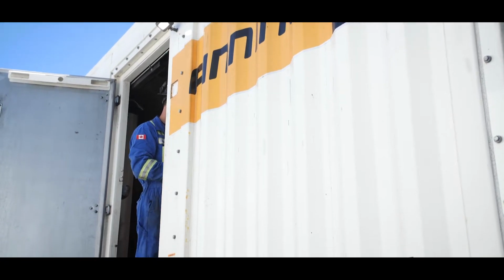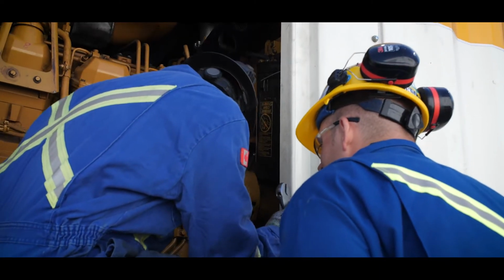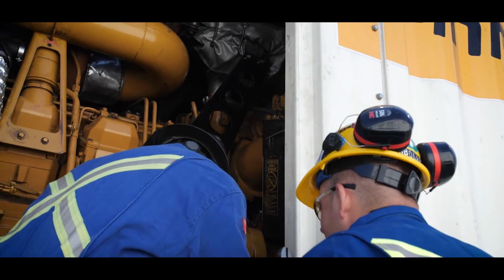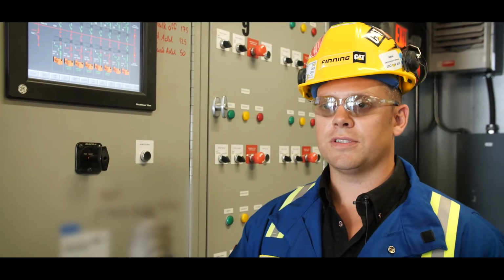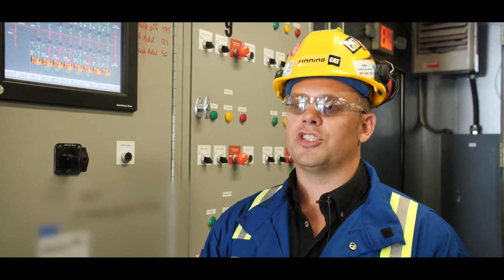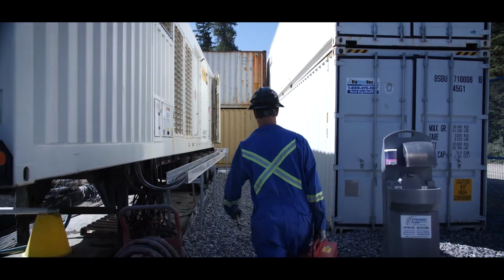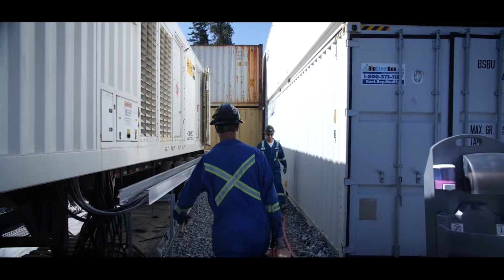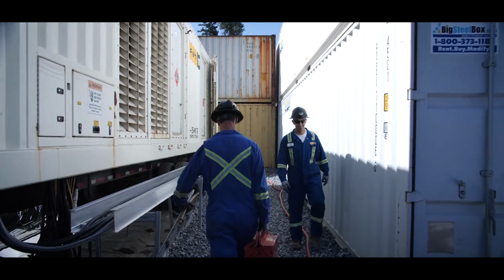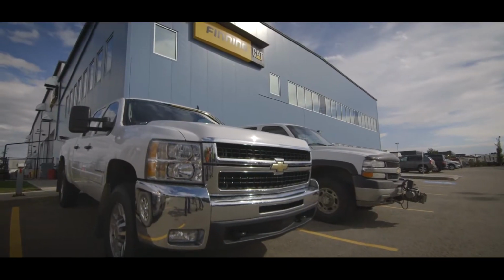There's also live monitoring of the units to see where they're at, so we can schedule maintenance intervals as needed. There is no interruption. All we simply do is change the priority sequence on our HMI and shut a unit off while another unit comes online and takes its place, and then we just continue on with servicing as needed.